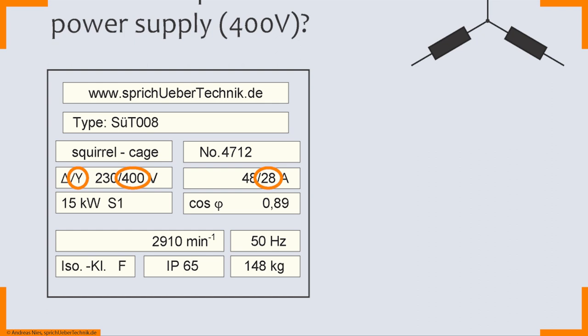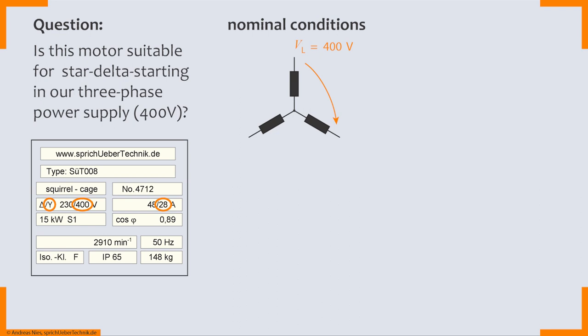Let me quickly write that down for you. So this part of the nameplate says the nominal phase-to-phase voltage is 400 volts. In other words, when connected to 400 volts, it's star connection, the motor runs at nominal conditions. Now what does that mean for the voltage at each of the coils of the motor? I will call it the coil voltage. In one of my previous videos I have already explained the factor square root of 3 and where it comes from.